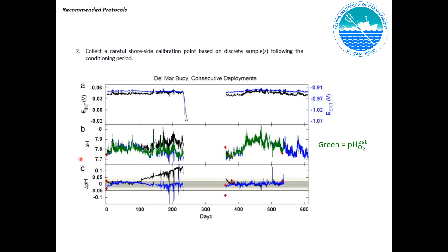And one of the other important points to make about this is that you want to do it after the sensor is conditioned. So there's a lot happening in this graph, but one of the points to make is that if you take a sample right at the point when a sensor is deployed and it hasn't conditioned yet, versus a sample after the sensor has been operating for a while, you can expect maybe to obtain different results if you're using just a single point to correct your time series.